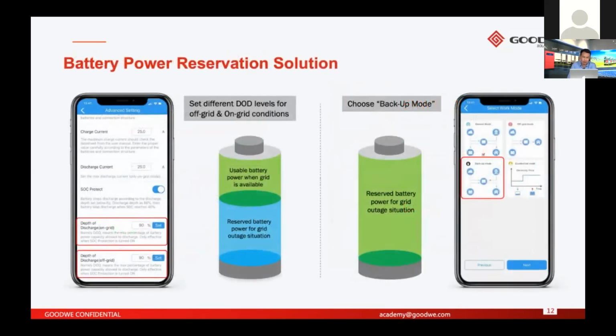And another solution is about battery power reservation. For this one, it's not just two solutions here. Here I just have two solutions, but we have more than two solutions. The first solution is the PV Master application. On the PV Master application, for the commissioning, you have the option to set different DOD of the battery. One is for on-grid use, one is for off-grid use.